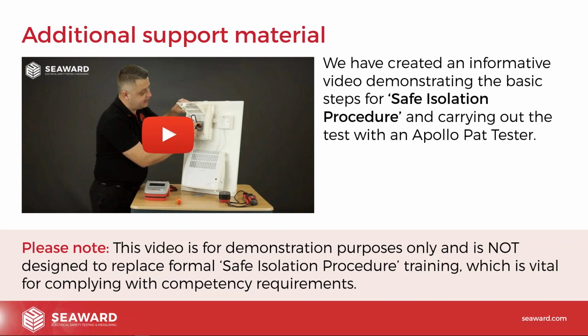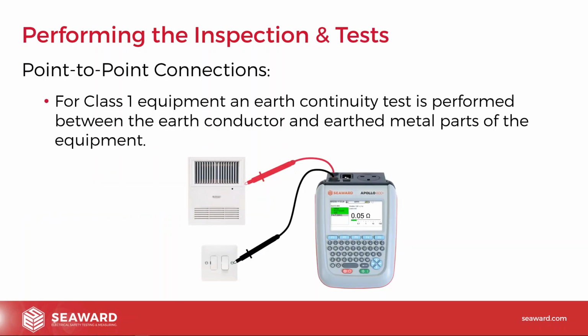we generally recommend, and this is where the Apollo comes into its own, being able to do the point-to-point tests, just using the croc clips and things like that, is actually a really good option. So the good thing with the Apollo is the ability to do point-to-point connections. What I mean by point-to-point is, instead of testing using the 3-pin main socket and one lead, you can put 2 leads in and test between the 2 leads, so it gives you the flexibility to test equipment that hasn't got a standard 3-pin plug.